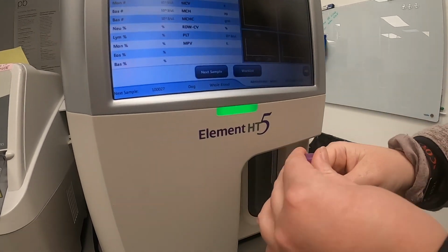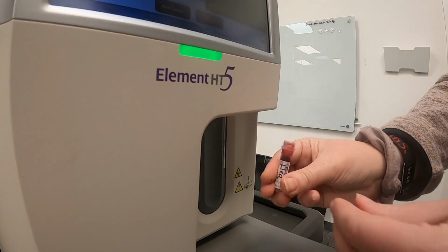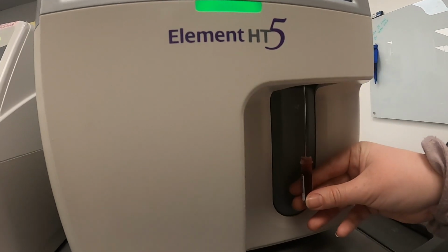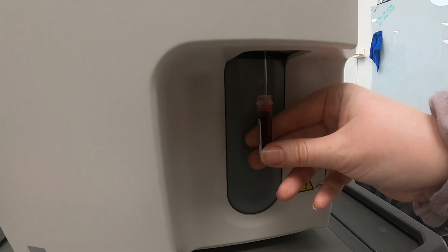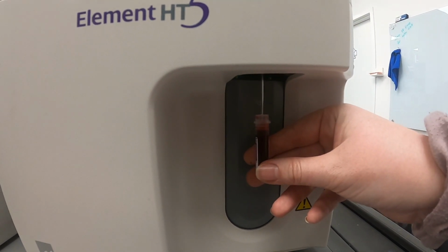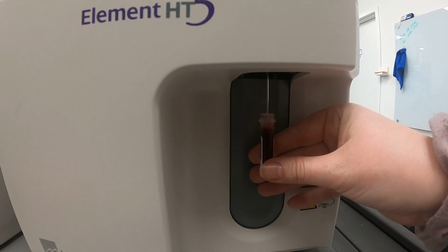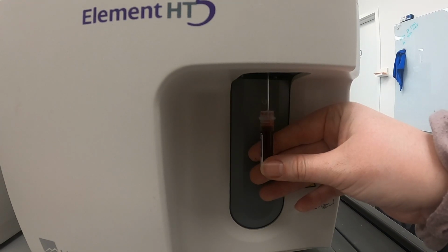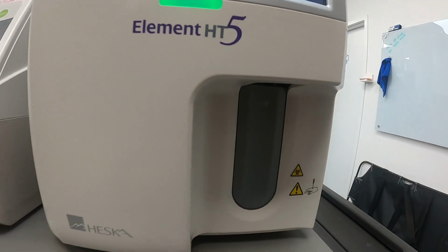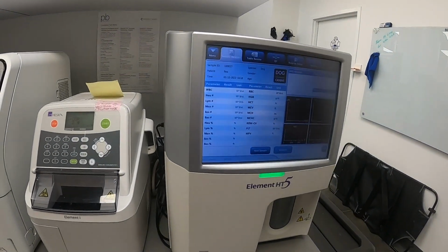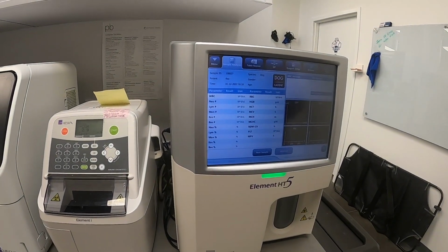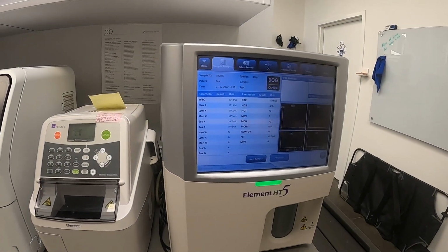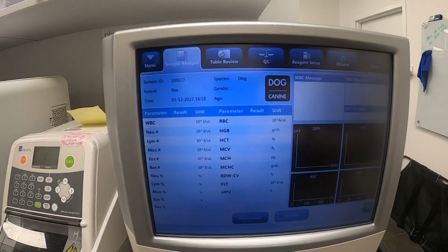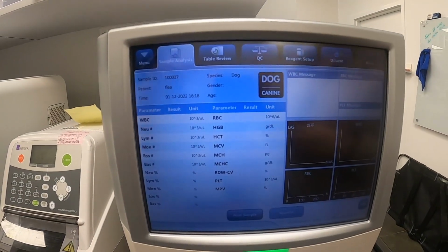Go. Okay, you're going to uncap your sample. Then we're going to introduce our sample to the probe. Again, not touching the bottom of the tube, but going down to about the middle of your sample. And once you're there, you're going to hit that back plate again. Let the machine aspirate the sample. Once the beep is beeped, then your sample is running. This usually takes about 2 to 3 minutes for results to come in, and they will pop up on your screen and will also transfer to the medical record.